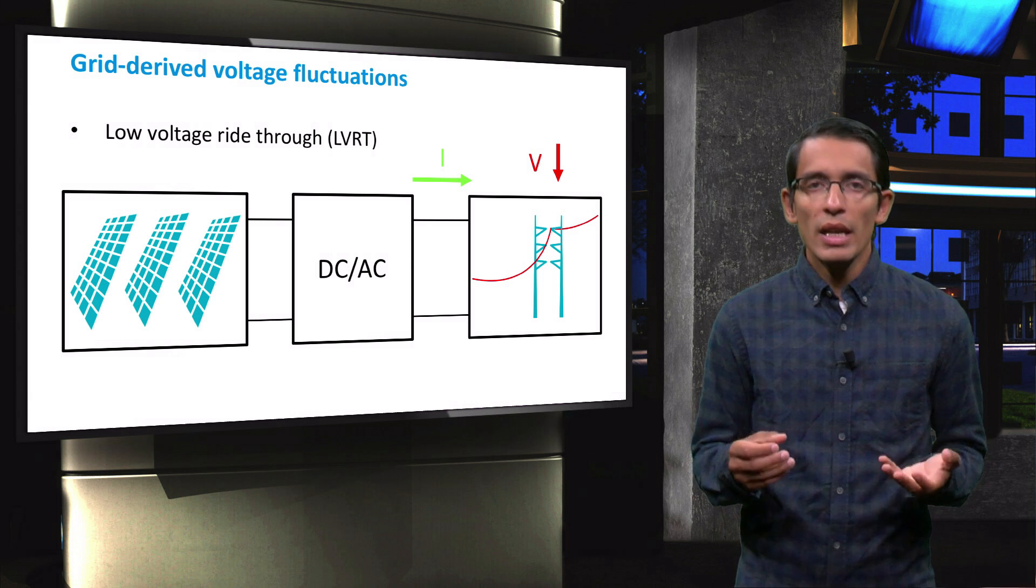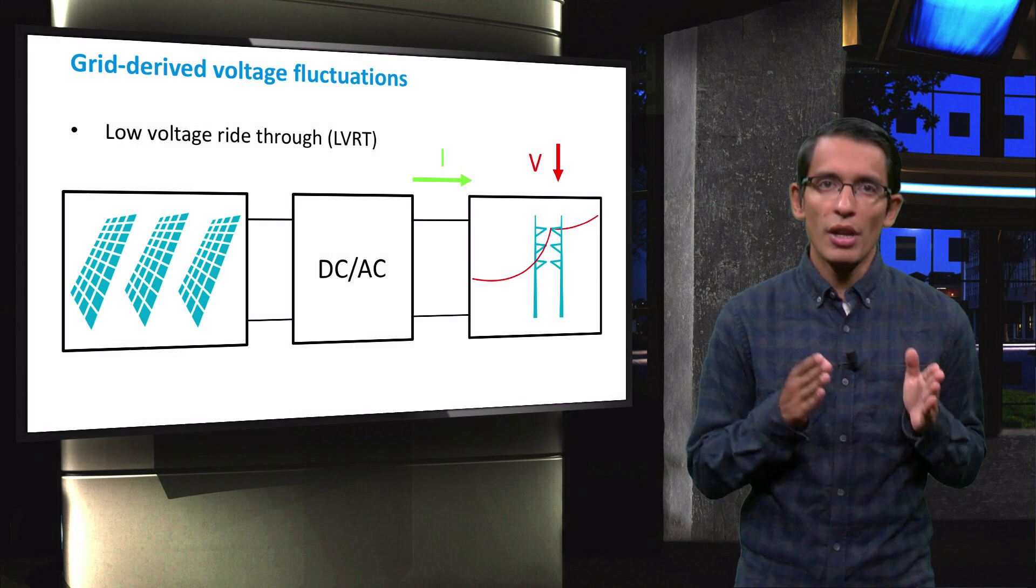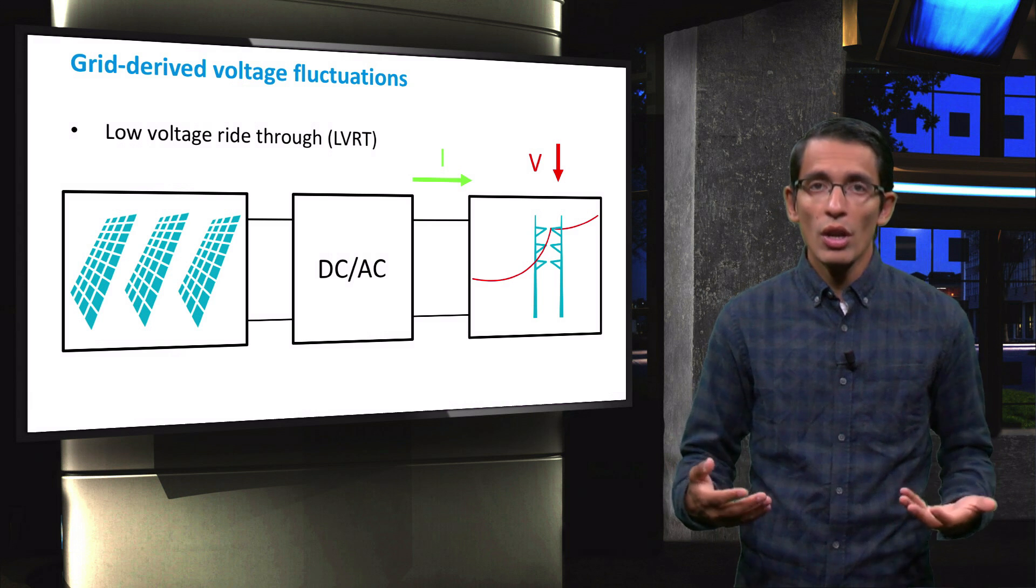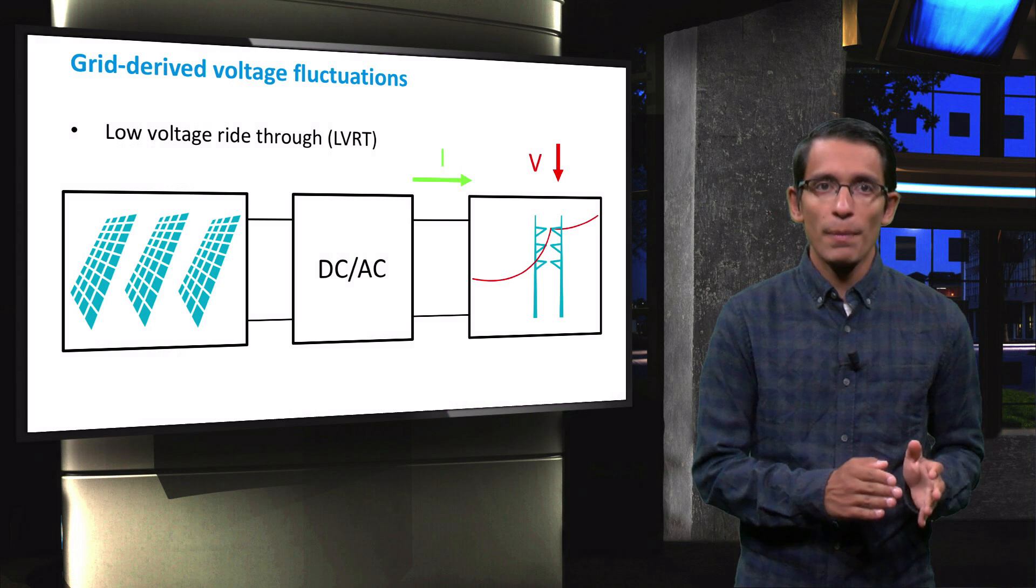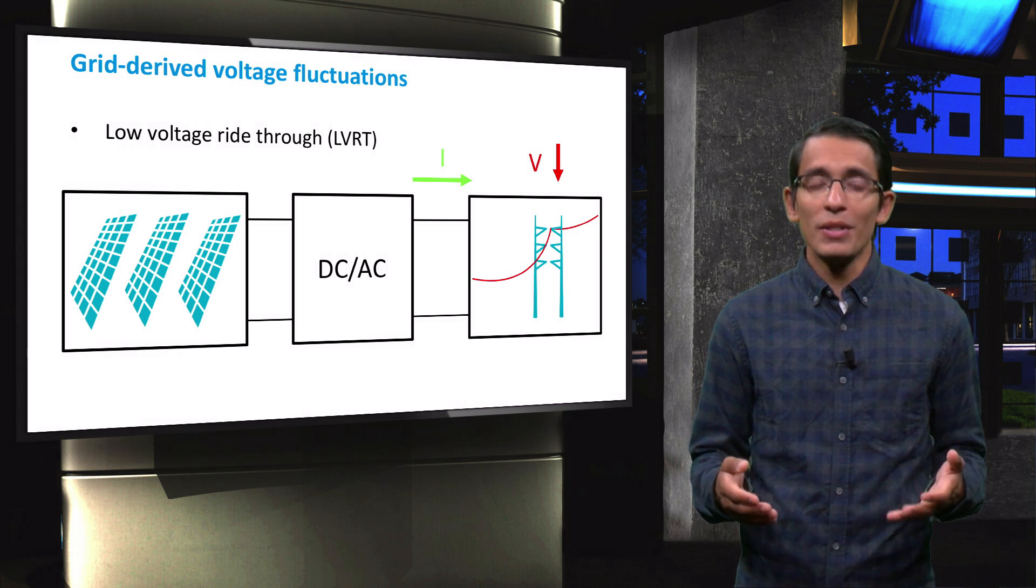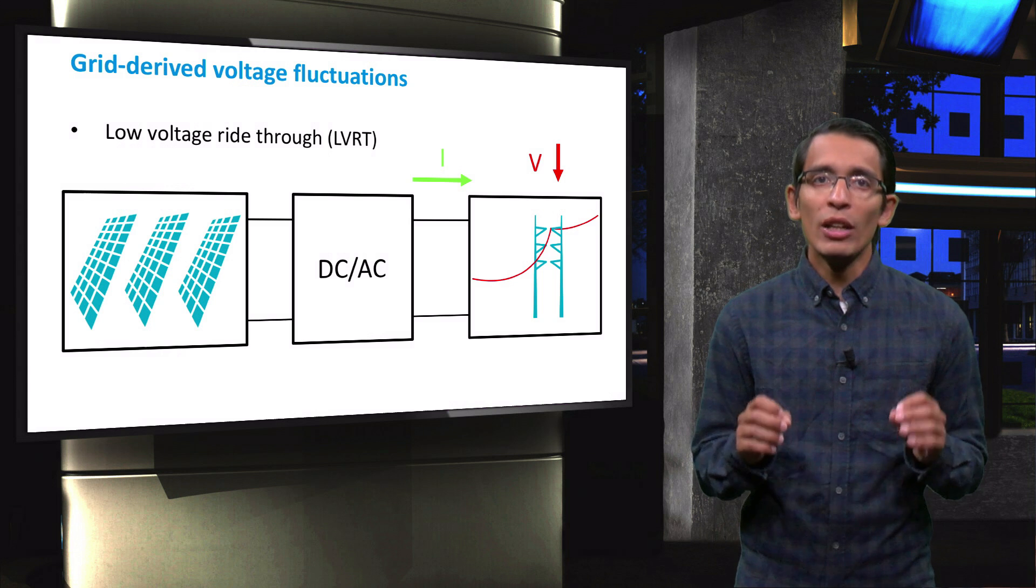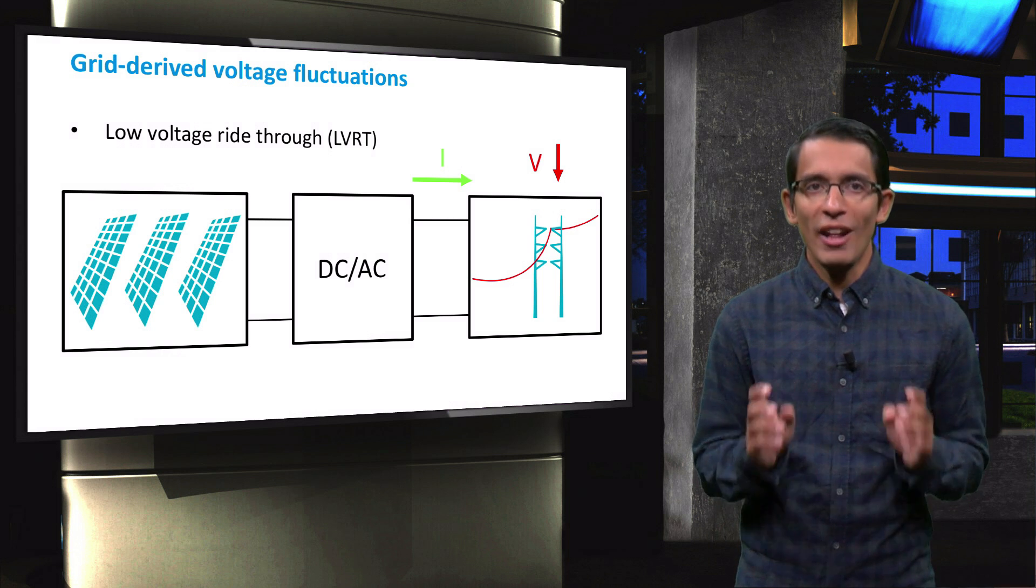Without LVRT, a small grid fluctuation would cause the PV to shut off. This, in turn, would cause a greater voltage dip, which would result in a cascading failure. Such a failure may result in a major blackout, so LVRT protection is essential to keeping grids healthy.